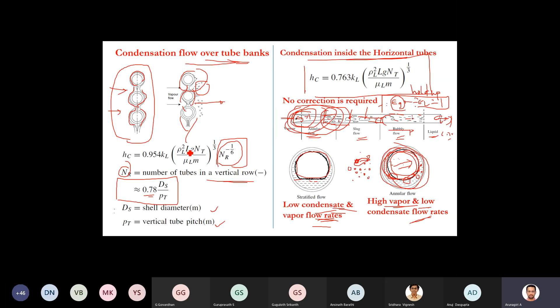Similarly, for condensation inside and outside vertical tubes, h_c is like this: 0.943 (k³ ρ² λ g / (L μL ΔT)) to the power 1/4. So this is for vertical tubes. This is slightly modified. For a tube bundle, you can modify this condensate loading τ. What is τ and how is it represented? τ is M divided by L and NT. This is condensate loading, τ equal to M by (L into NT). M is in kg per second, L is per unit meter, NT is number of tubes, so kg per meter second, like this you can calculate. So the equation is now simplified. ρL is replaced by ρL into (ρL minus ρV) g, where the denominator has the condensate loading. So you can use this equation also.